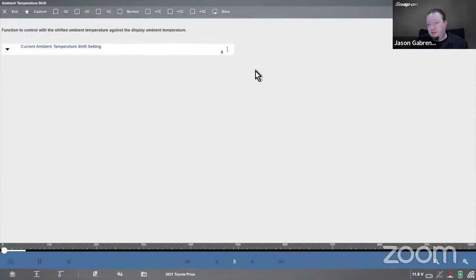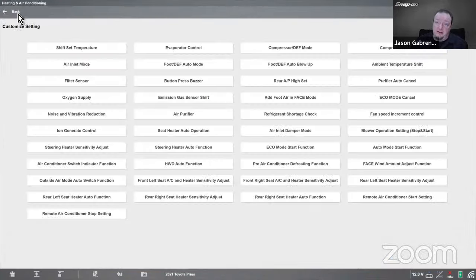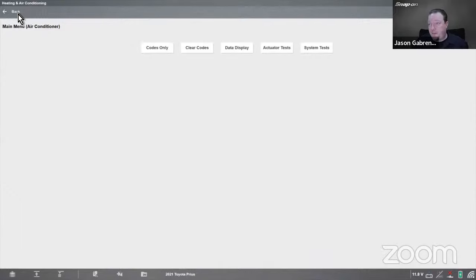Ambient temperature shift. It's going to change it plus or minus 3 degrees Celsius. Shifted ambient temperature against the displayed ambient temperature. So if you need to calibrate that, do that as well.